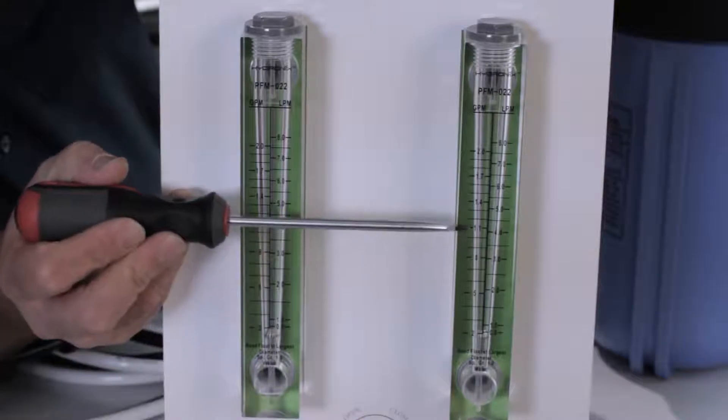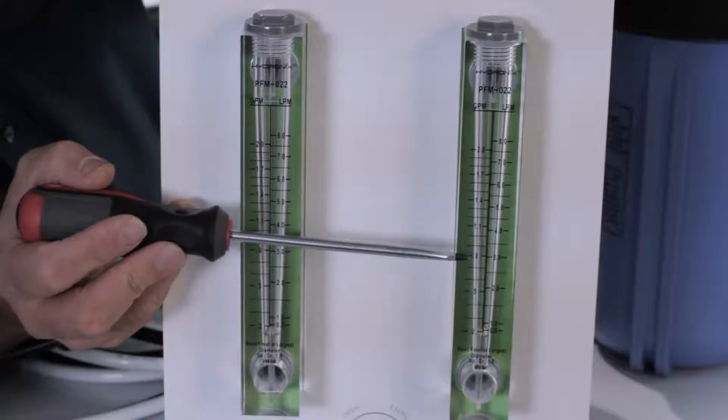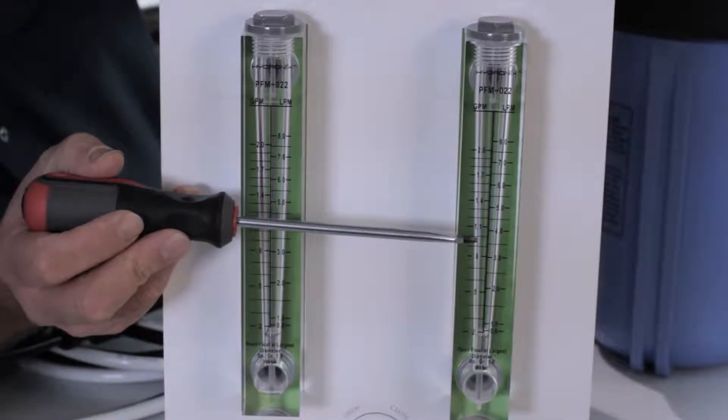It's not when they both read one gallon a minute, which some people mistake. It's when they're equal. One part drain to one part permeate RO water.